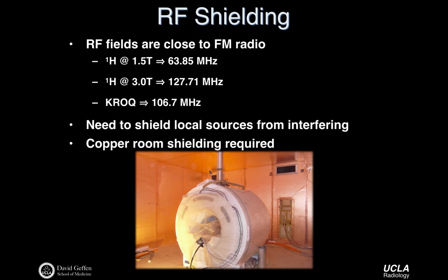And so the rooms, somewhat beautifully, have to be clad in copper as well to form a so-called Faraday cage. The reason for that is to keep stray electromagnetic radiation that's outside of the room from getting into your coil, and causing contamination of the signals that you're measuring. So, in some sense, it's really kind of pretty, but it's also really expensive to build a Faraday cage after you've already shielded the room, before you throw up the drywall and paint it.